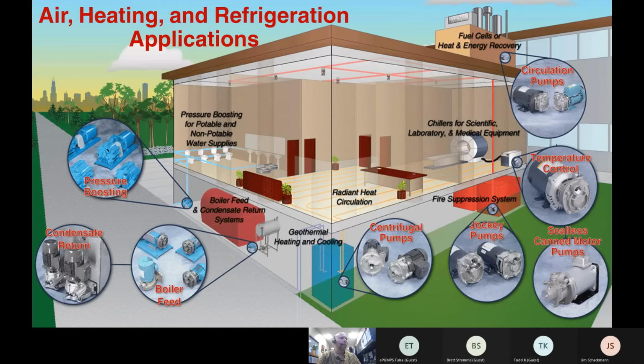Well, you don't want a leak causing all of them to accidentally go off. So the leaks come from a drip in the system, or a backflow in a check valve somewhere, or maybe the city is doing something and you don't want the water flushing back and setting off the main fire pump. So we have a jockey maintenance pump that will simply turn on when the water in the pipeline hits a certain pressure, and turn off again when it's recharged to that higher pressure.